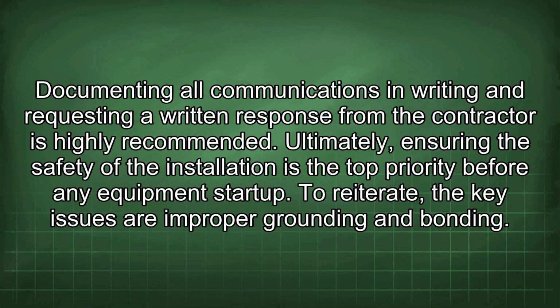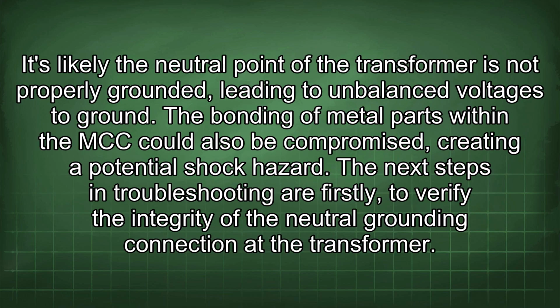To reiterate, the key issues are improper grounding and bonding. It's likely the neutral point of the transformer is not properly grounded, leading to unbalanced voltages to ground. The bonding of metal parts within the MCC could also be compromised, creating a potential shock hazard.